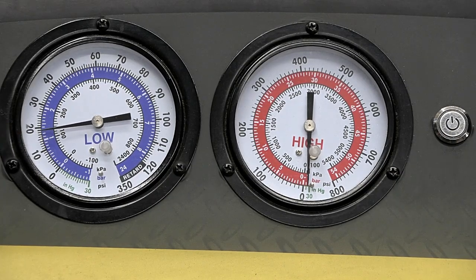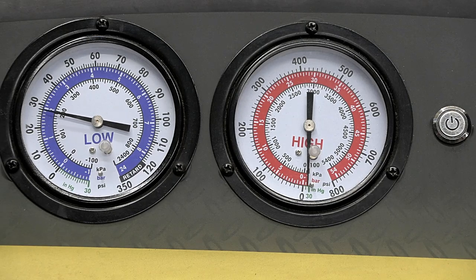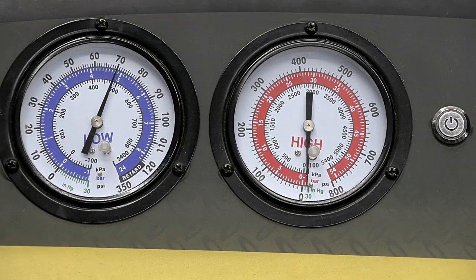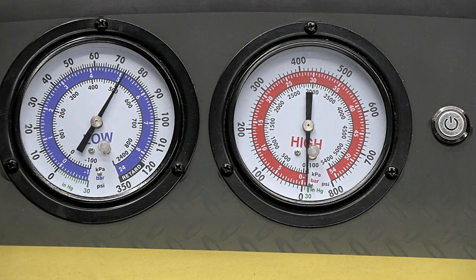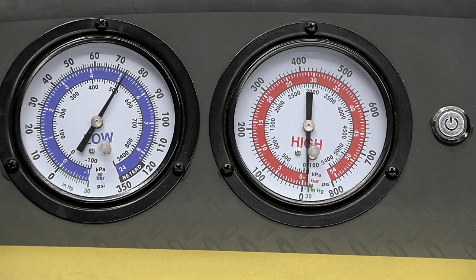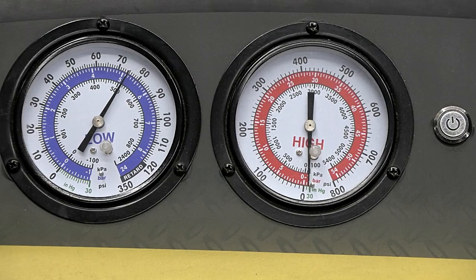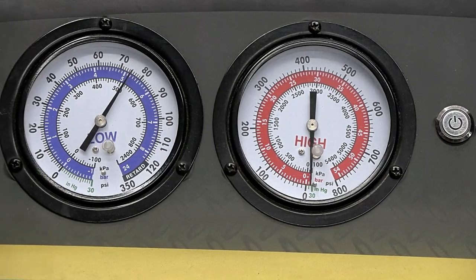Watch this now, you see the pressure went up? That is telling me, basically, I have pressure in the system, and we should get up to ambient temperature if the system is totally full. So right now in the shop, it is roughly 68 degrees up top. So down here, we're pretty much 68, 70 degrees. 1 pound of pressure roughly is 1 Fahrenheit. So may have a little bit of an overcharge.